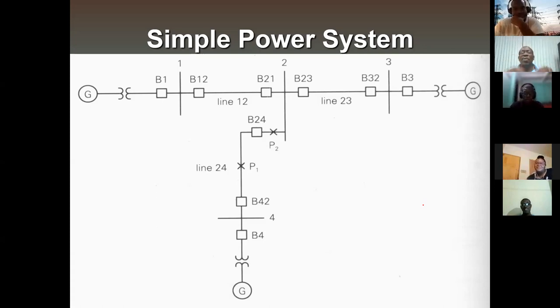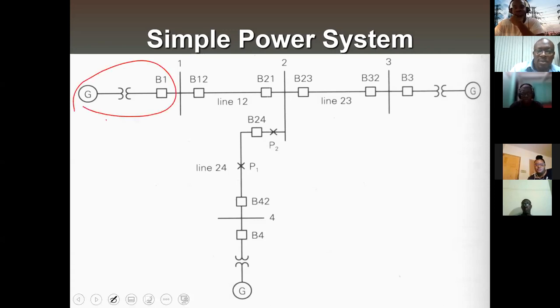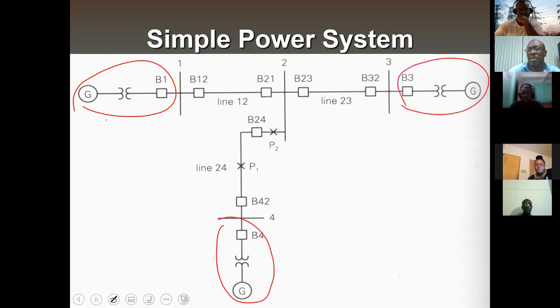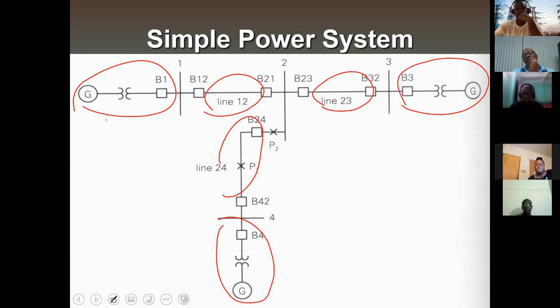So we'll have to look at the number of components you have. Of course, for the generator transformer, we can make that into a single zone. So each of these would be a zone. So we have three. We have these transmission lines, counting components. So already we've gone 1, 2, 3, 4, 5, 6 zones.